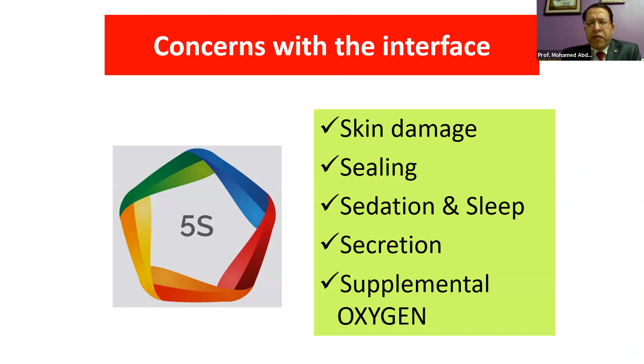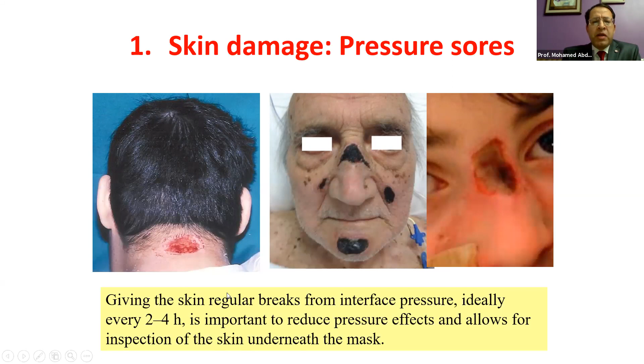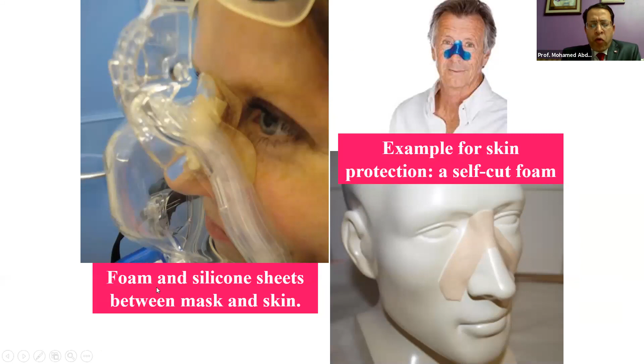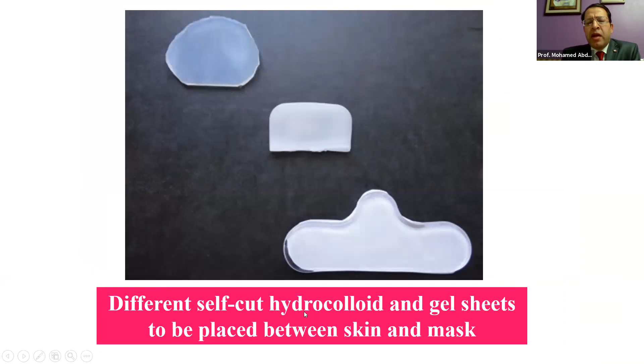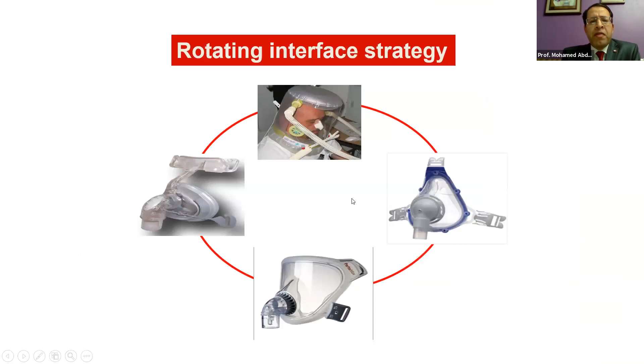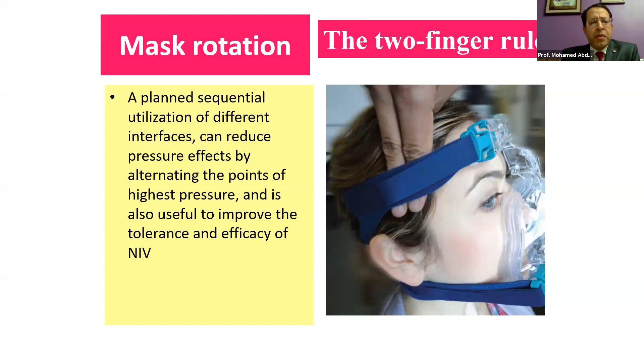So skin damage can be prevented by giving the skin regular breaks from interface pressure, ideally every 2 to 4 hours, or rotating the mask, or using what's called silicone sheets or foam. It will minimize the pressure manifestation. Different self-cut hydrocolloid and gel sheets can be placed between the skin and the mask, or use the rotation of the mask in order to minimize the pressure sore. And use the 2-finger rule, which means that you put 2 fingers between the headgear and the face, allowing your finger to pass easily through it.